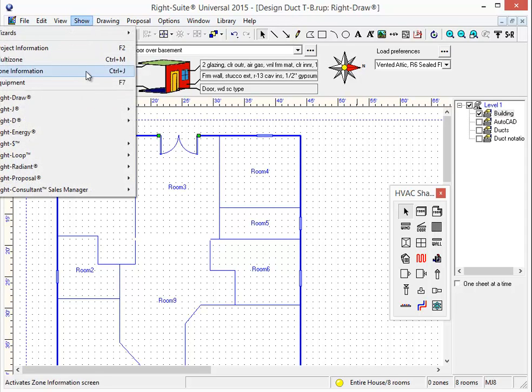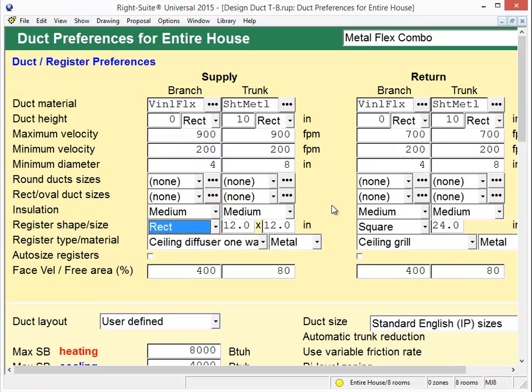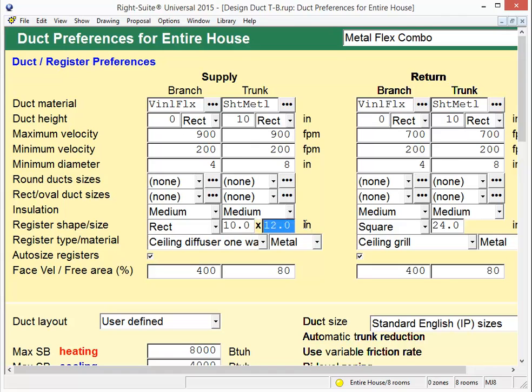The first feature we're going to look at is Right-Suite's ability to auto-size a register. Simply check the box for auto-sizing registers and set your most common grill size. The program will use the smaller of the two rectangular dimensions to size off of. For instance, if most of my grills will be 10 by 6 and I have a register with a larger amount of airflow, it will give me a 12 by 6. If I set it for a 10 by 4, it might give me an 8 by 4 if I need less CFM.